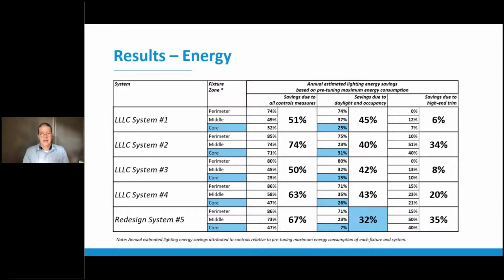And that was a determination made based upon experience in the field that once you're more than 2 window head heights away from the window, and I think we were about 2.5 window head heights away for that center zone, we just decided not to apply the daylight dimming. Whereas the LLLC solutions have daylight sensing on board, and they were capturing some savings from relatively modest amounts of daylight into that core zone area. So I think an interesting differentiation. It's a fair question whether we made the right choice from a redesign standpoint. Nonetheless, it is the choice we made, and these are the results that came from it.